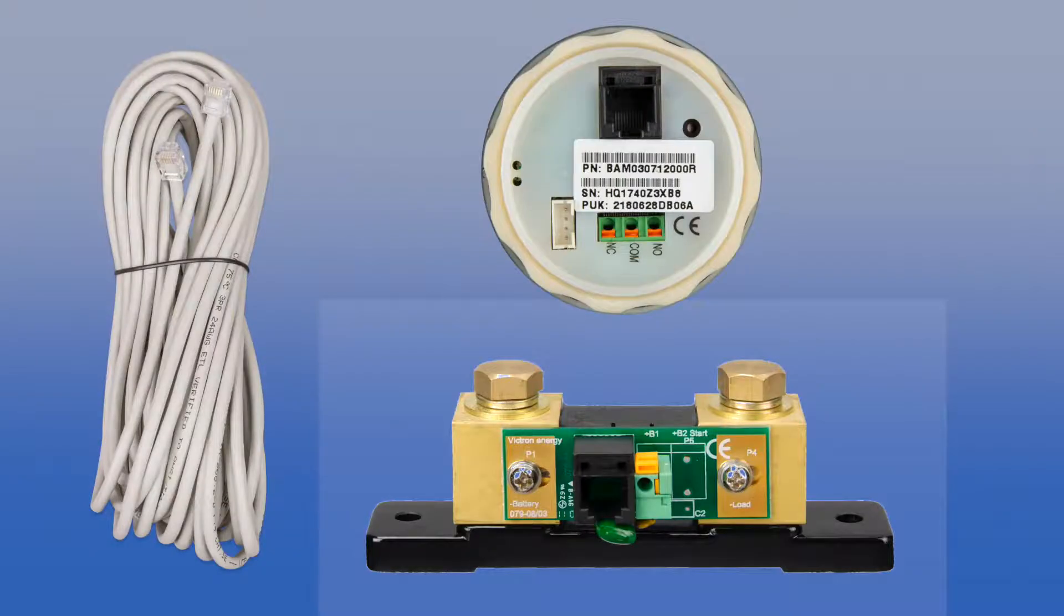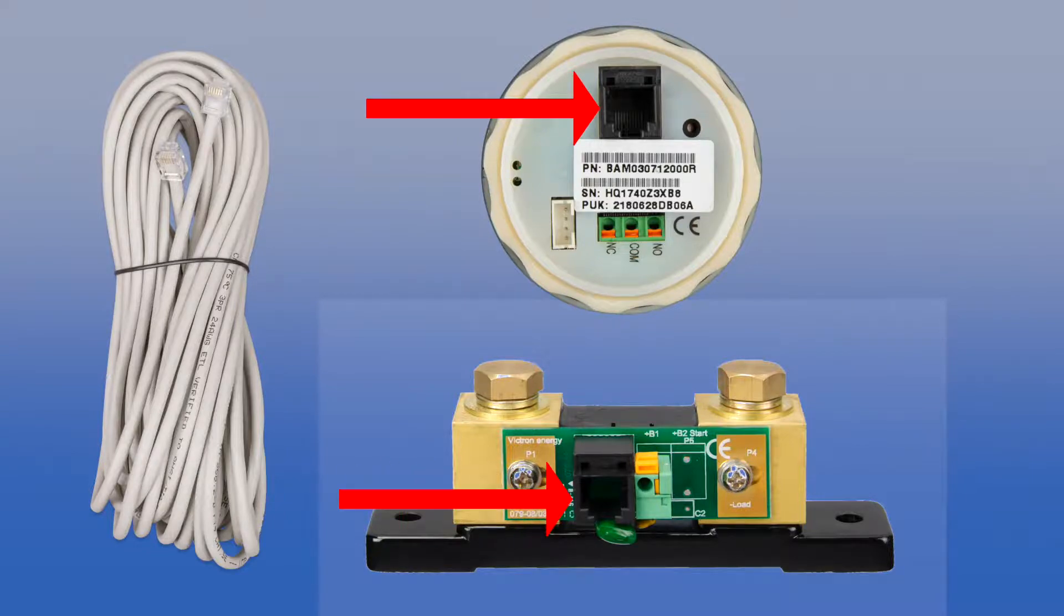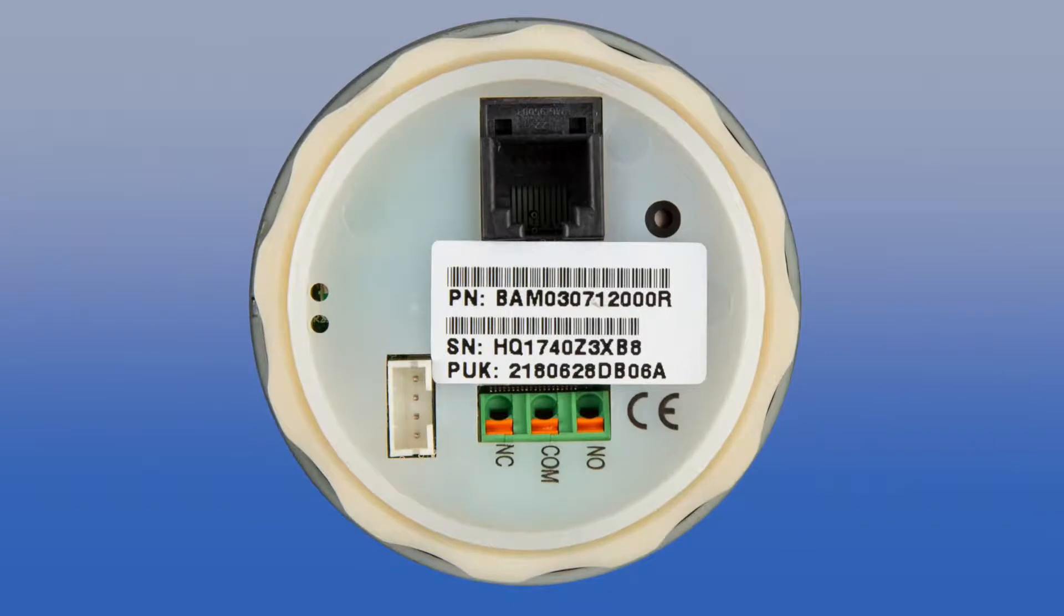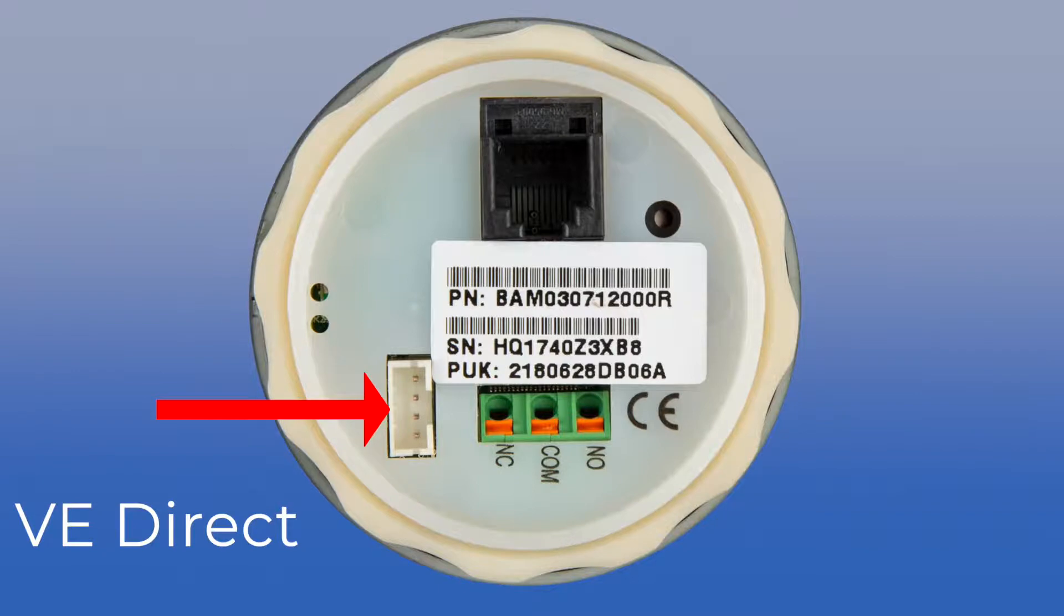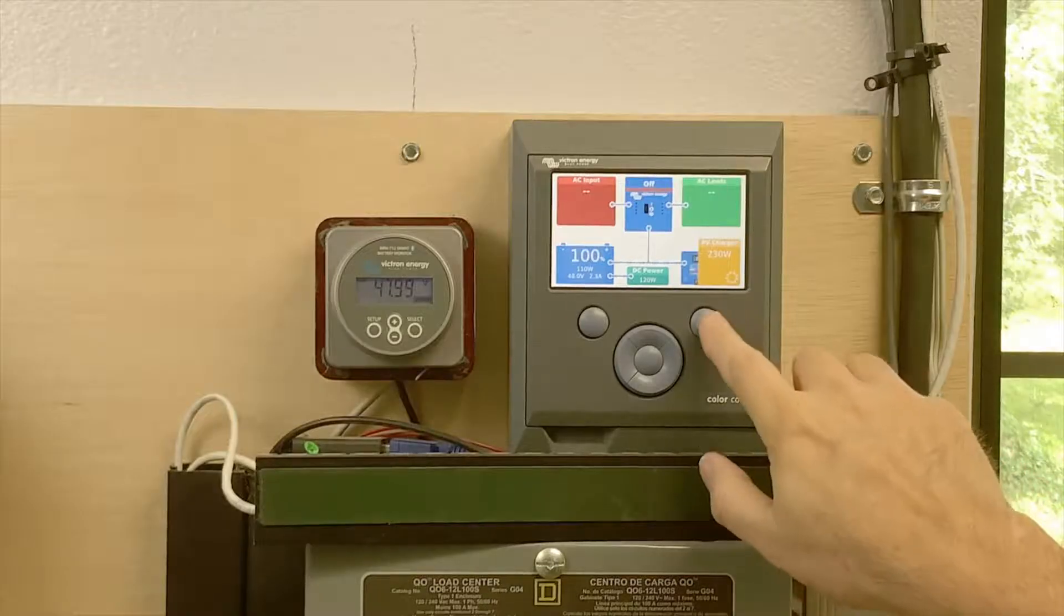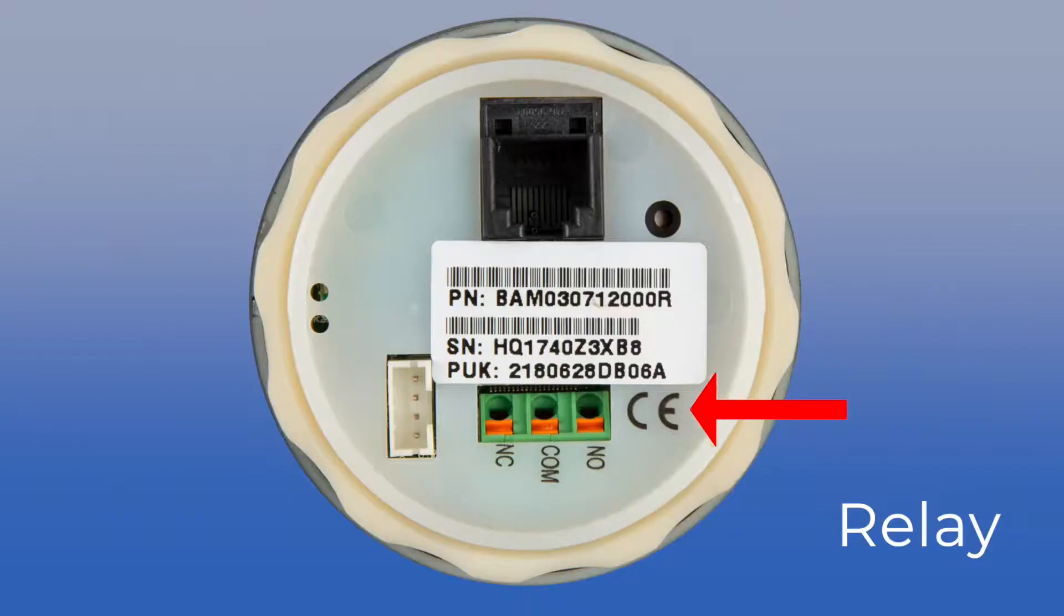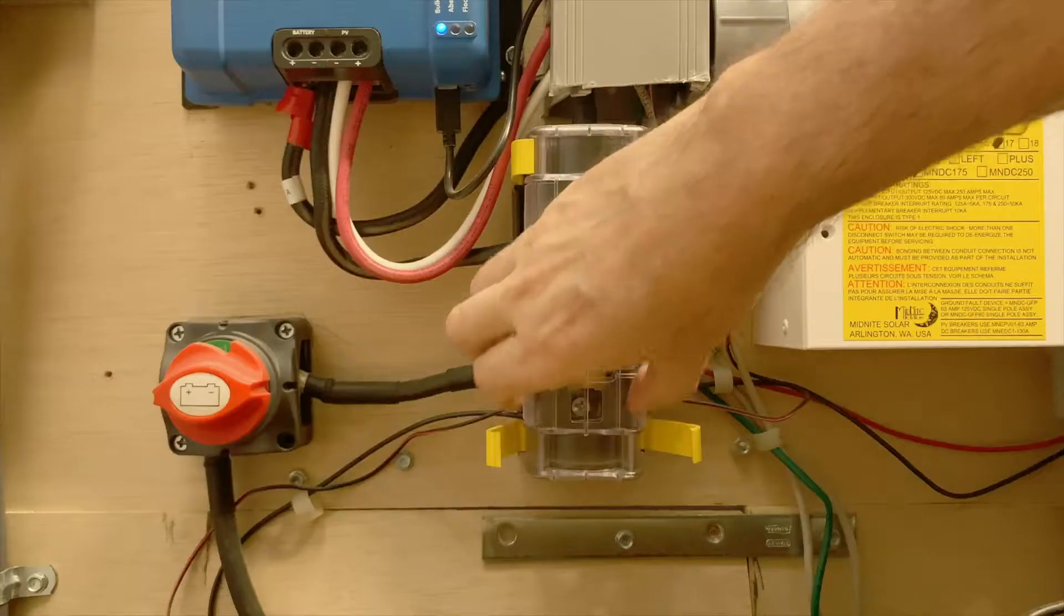Depending on your situation, you may need to connect any cables before mounting. The main communication cable between the monitor and the shunt is an RJ12 standard telephone cable, which is supplied, and many people find that this is the only cable that they need. Optionally, you may also hook up a VE direct cable or wires to the relay. The VE direct cable allows the battery monitor to send information to a GX unit like the color control. The relay can be programmed to turn on or off under certain battery conditions, useful for things like starting a generator and also other uses.